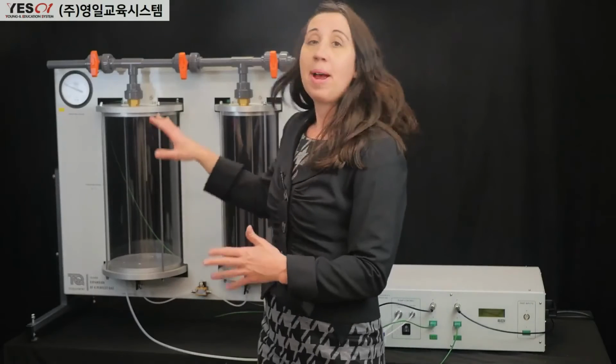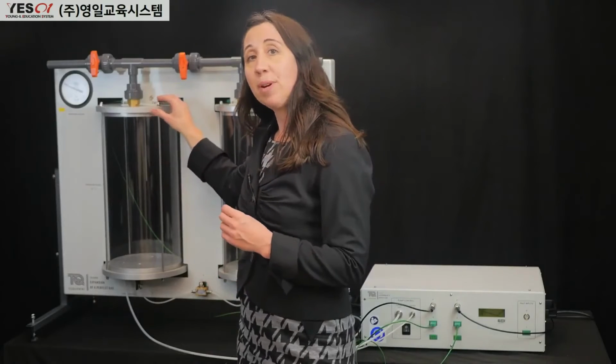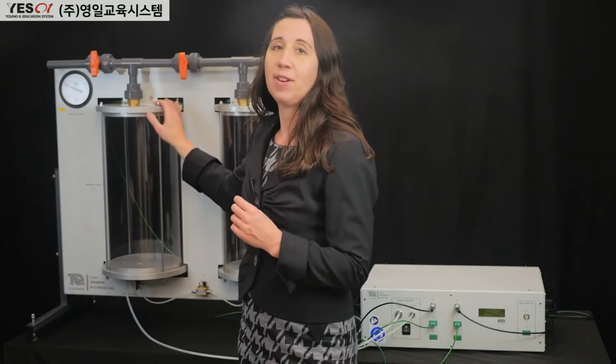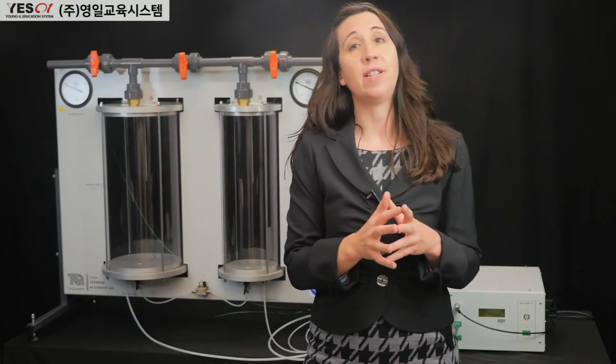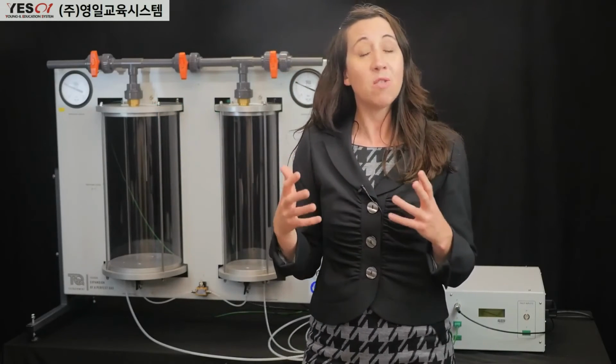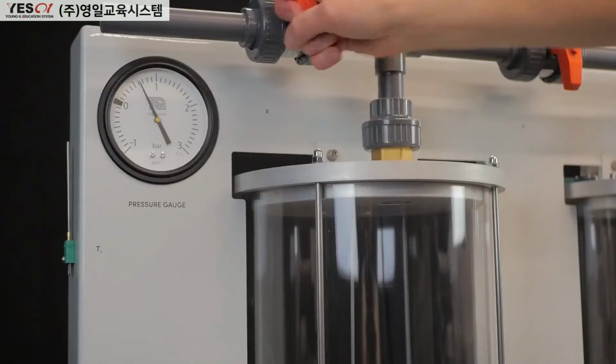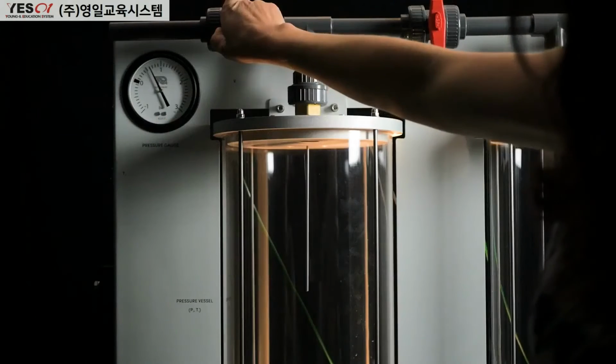Safety is always paramount, which is why the flange on the pressure vessel holds a pressure release valve to prevent it becoming overpressurized. Another note on safety is that when the valves are opened, they can reach up to 100 decibels, which is why I'm wearing ear defenders here.